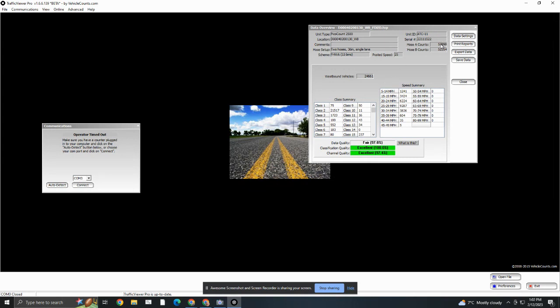The thing to note here is that was a pretty long dwell, 140. And you see the A hose counts and the B hose counts. These are the counts that are left after filtering, and usually it's the dwell that's the filter. There's a couple other things, but the dwell is the main one. And it says before that, the counter actually recorded 95,754 hits, but only 52,000 are going to be used for processing. Likewise here, 93,270, but only 52 something is going to be used.